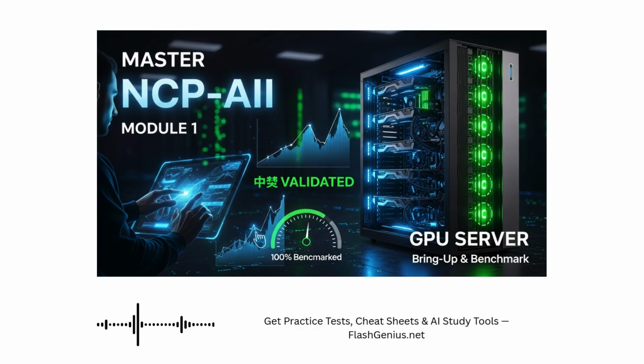So if I made a mistake and ran a 7-meter DAC cable across the aisle for my 200-gig link, what would happen? You'd get marginal signal quality. The link might come up, but the signal-to-noise ratio would be terrible. And this is where validation is so important - you can't just check if the link is up, you have to look at the error counters.